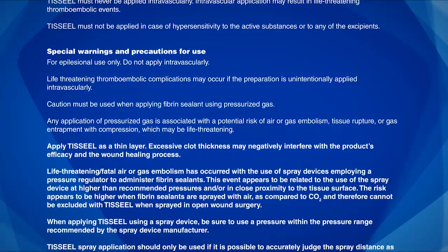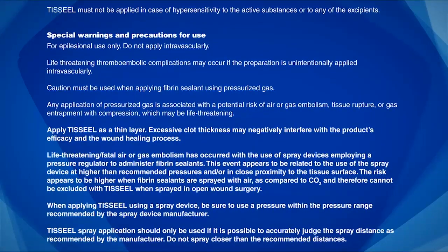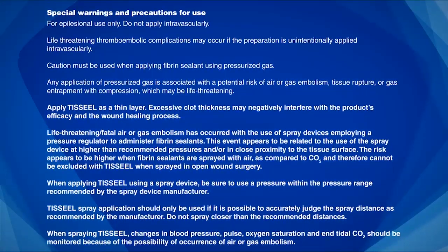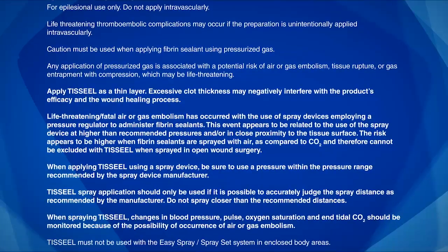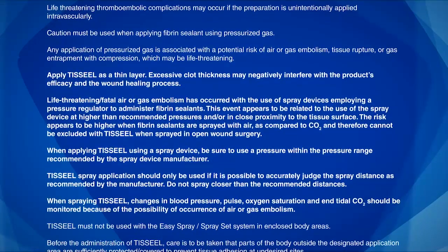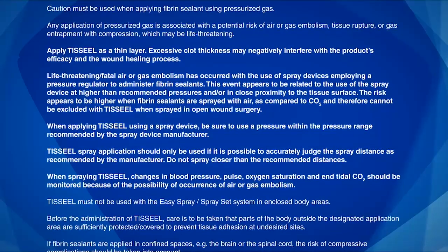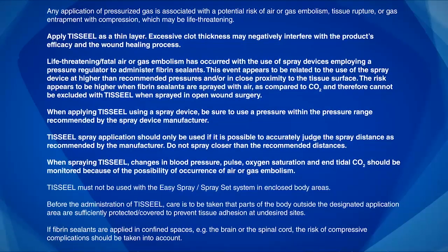Apply TISSEEL in a thin layer; excessive clot thickness may negatively interfere with the product's efficacy and the wound healing process. Life-threatening, fatal air or gas embolism has occurred with the use of spray devices employing a pressure regulator to administer fibrin sealants. This event appears related to use of the spray device at higher than recommended pressures and/or in close proximity to the tissue surface. The risk appears higher when fibrin sealants are sprayed with air as compared to CO2, and therefore cannot be excluded with TISSEEL when sprayed in open wound surgery. When applying TISSEEL using a spray device, be sure to use a pressure within the range recommended by the spray device manufacturer. Spray application should only be used if it is possible to accurately judge the spray distance as recommended by the manufacturer; do not spray closer than the recommended distances.